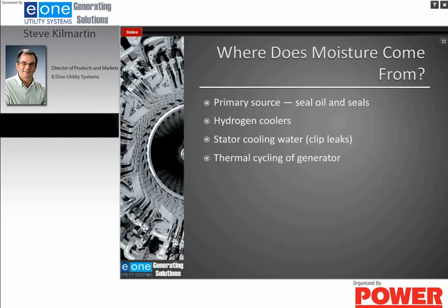Where does moisture come from? The primary source is the seal oil. In many large power plants where you have steam turbines, in some cases they share the oil source. So the steam seal or bearing on a steam turbine will absorb moisture from the steam and then be carried over to the generator where it goes into the generator.